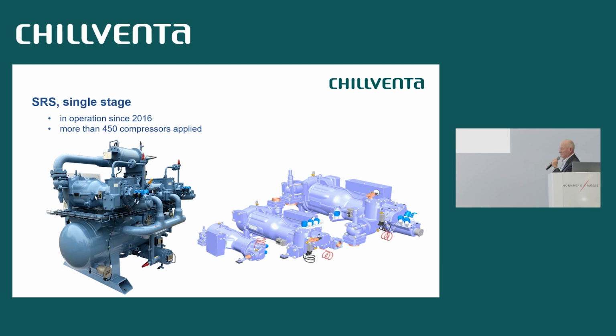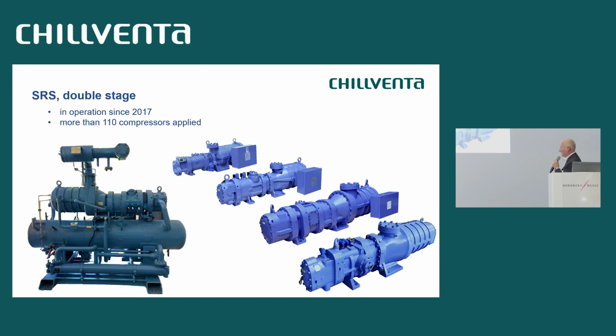We have had these compressors in operation for more than 8 years. We're running them on more than 450 compressor packages meanwhile, since more than 8 years. And it is a stable solution, stable motors, which are working reliably. Same thing can be said, just in lower volume and numbers, on the low temperature applications, double stage semi-hermetic compressors. More than 110 compressors are applied meanwhile since 2017.